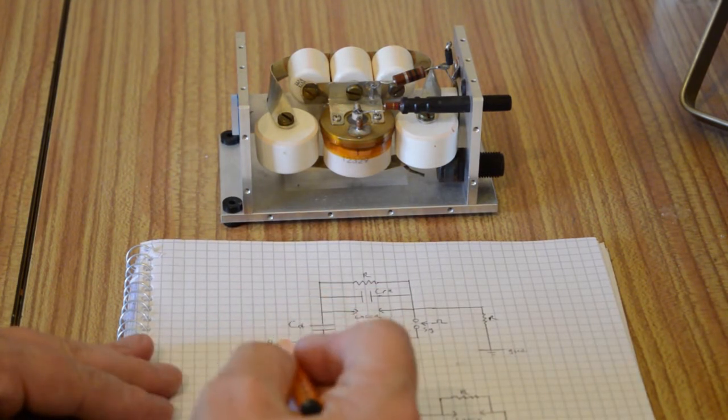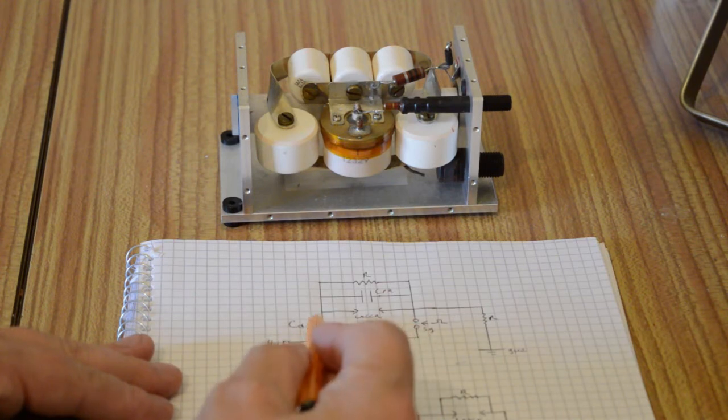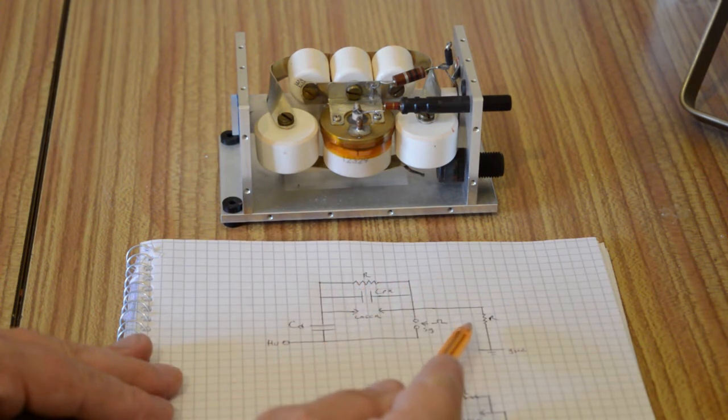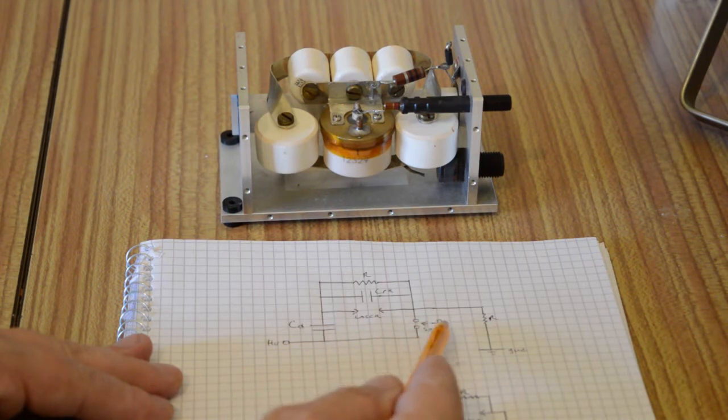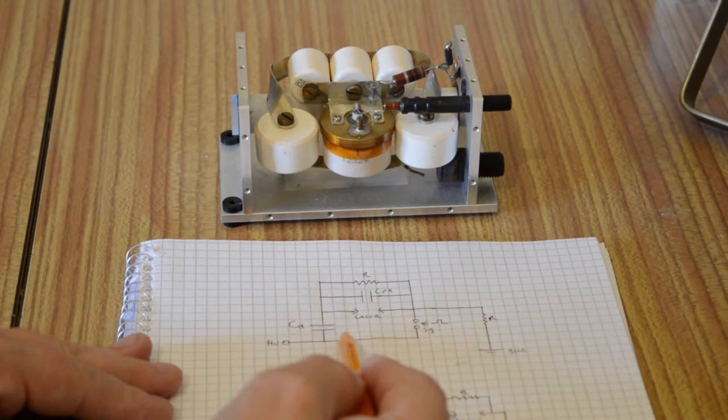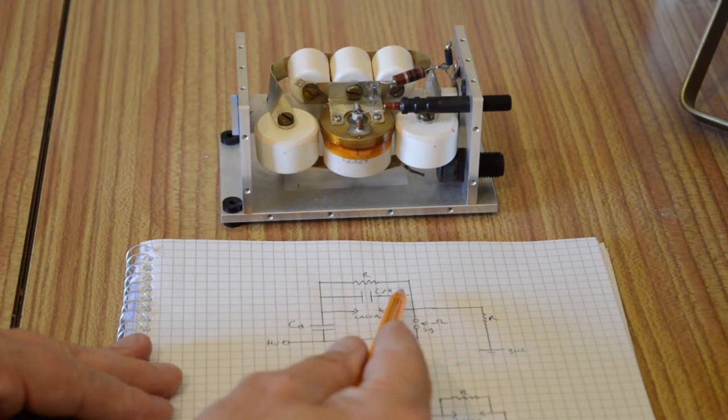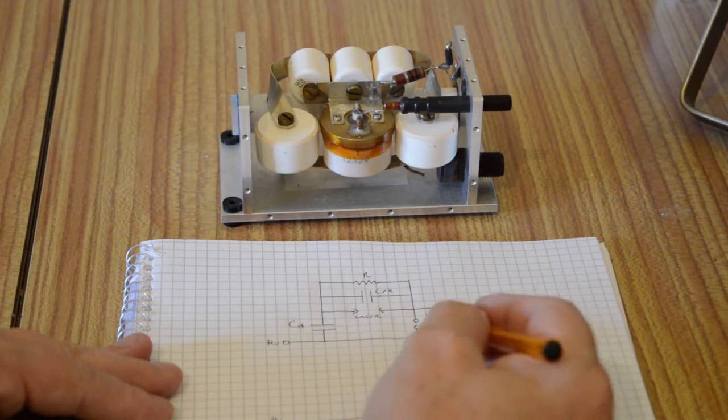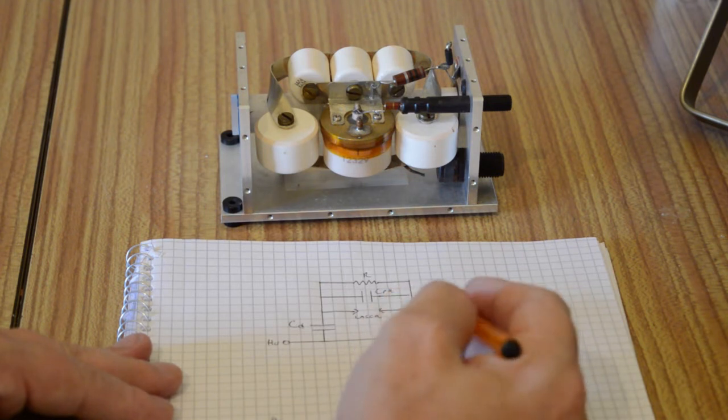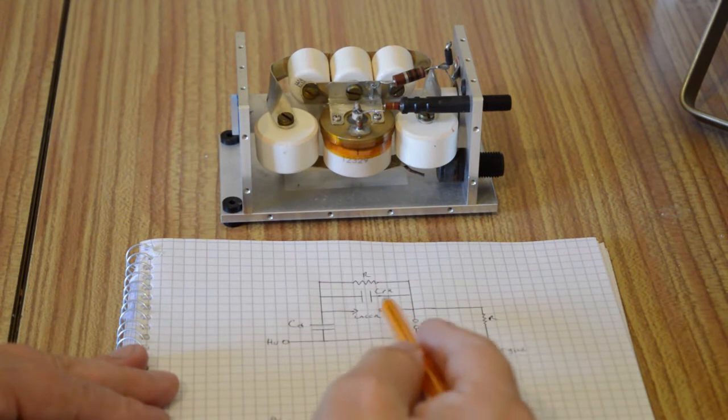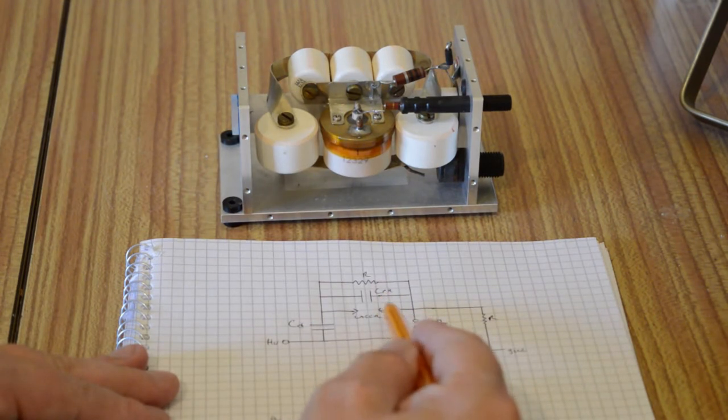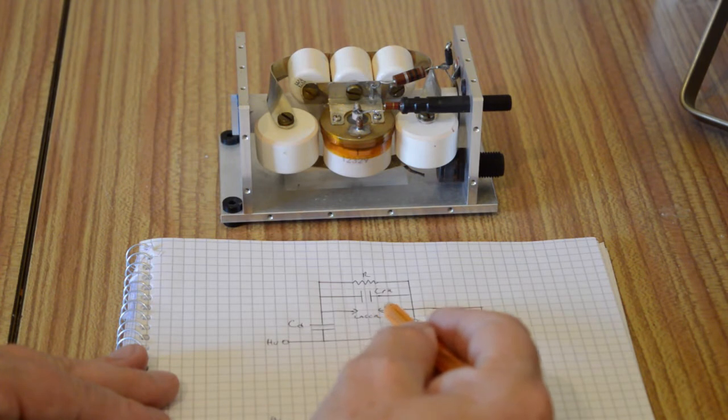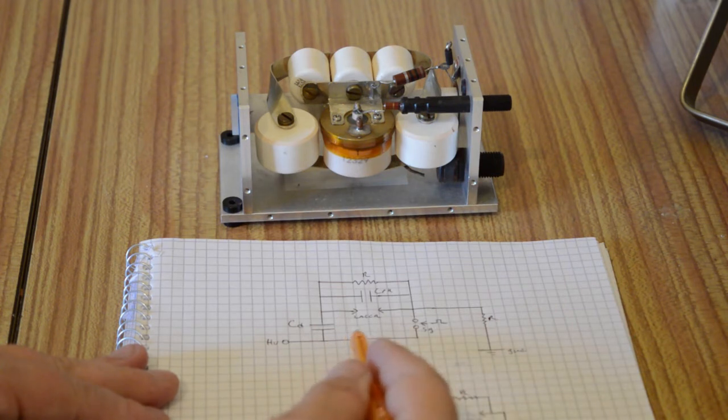So when we charge the circuit, we put high voltage in here, 17,500 volts. CD, the dumper, charges up via these resistors up to the charging voltage. When the spark gap fires, we apply a high voltage pulse to this spark gap, the contents of this capacitor transit the spark gap and charge up the peaking capacitor very, very quickly. The spark gap conducts in maybe 5 to 10 nanoseconds. The job of the peaking capacitor is to take that relatively slow pulse and peak it to a point where we can get a very fast discharge across the laser tube. So once the peaking capacitor reaches its peak voltage, the laser tube conducts and the discharge that forms between the two electrodes is hopefully short enough to populate the upper laser level and start lasing.